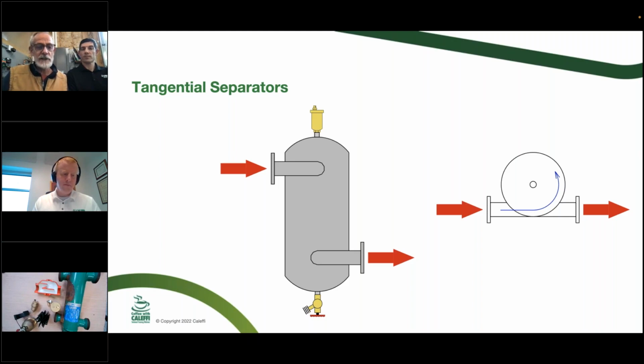So it doesn't necessarily need to be in the secondary loop. It wants to be in the hottest point in the system. But no, you can put an elbow on the inlet or the outlet side of this type of separator, the Discal, for example, or the combination Discal dirt. And that's why that bell is so big. If you take one of the separators that we show there and put it next to some of the other ones on the market, or even an air vent or something like that, it's big because we really want that velocity to slow down quite a bit.